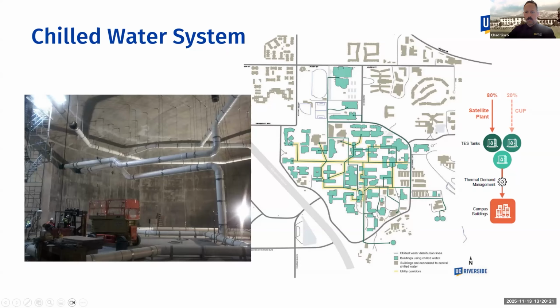The central plant is right here in the center of campus. So after they did that, around 2005, our second thermal energy storage tank was installed. TES-2 is 2.7 million gallons, capacity about 24,000 ton-hours. And it was also tucked into the hills to the south here. Here's TES-2 and 3, and here's TES-1, if you can see my little cursor on the screen.